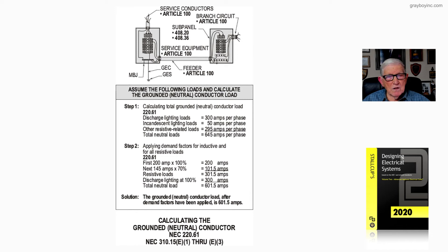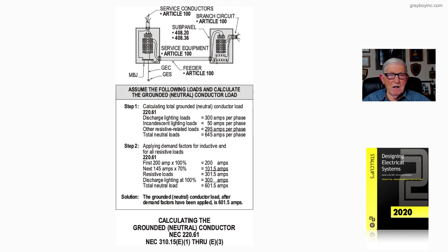A demand factor can only be applied to resistive loading. So in step two under 220.61, we separate the resistive and inductive loading. The first 200 amps of the resistive load is taken at 100%, which is 200 amps. The next 145 amps is taken at 70%, giving 101.5 amps. Adding those two resistive loads together gives 301.5 amps. The discharge lighting must be taken at 100%, which is 300 amps.